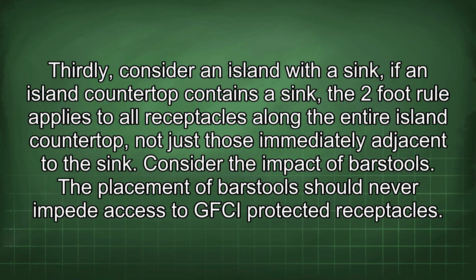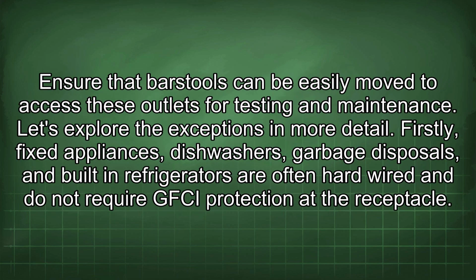Thirdly, consider an island with a sink. If an island countertop contains a sink, the 2-foot rule applies to all receptacles along the entire island countertop, not just those immediately adjacent to the sink. Consider the impact of bar stools. The placement of bar stools should never impede access to GFCI-protected receptacles. Ensure that bar stools can be easily moved to access these outlets for testing and maintenance.